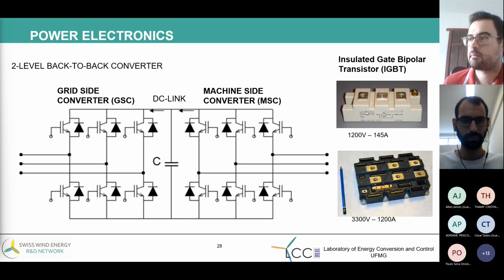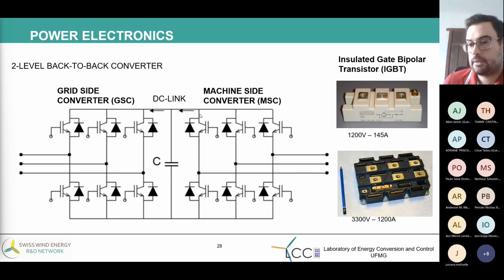More questions? Does the power converter system need to be placed on top of the tower, or can it be underground? It depends on the technology. Albins is asking where the power converter is placed. Some manufacturers place the power converter in the nacelle, right next to the generator, and there are companies that prefer to put the converters at the bottom of the tower. There are advantages and disadvantages for each one.